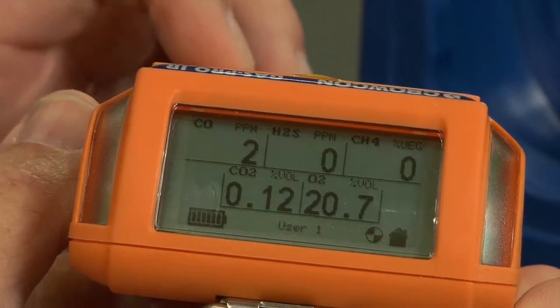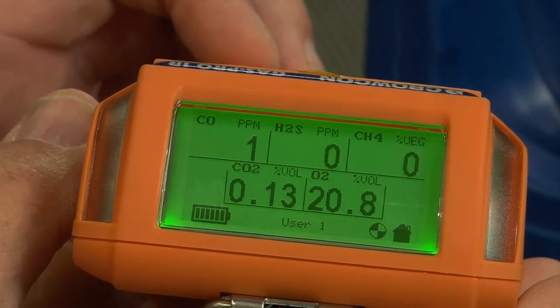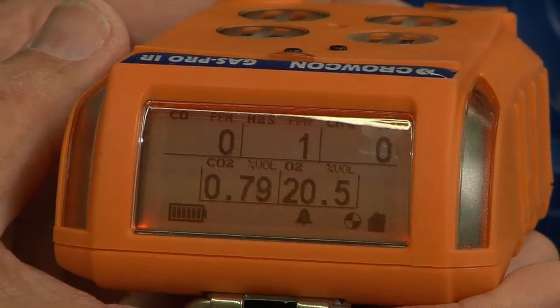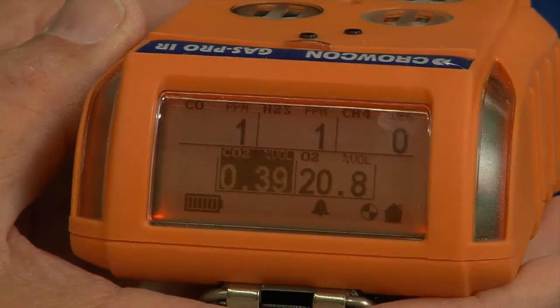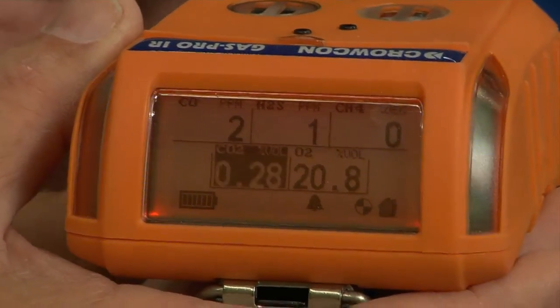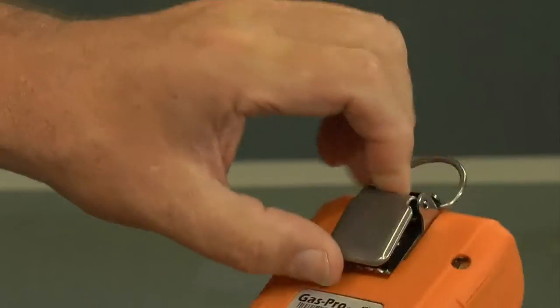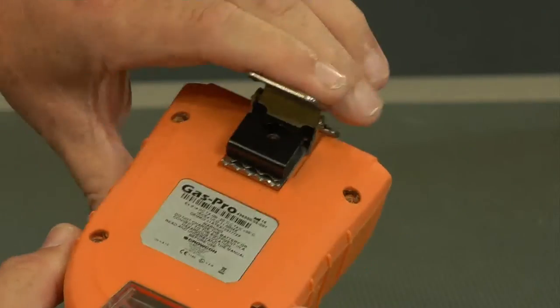Now I do my breath test — and now we are in the set alarm area. It alarms very strongly and is very loud, so that you can hear it in loud environments. I turn the sound off, but the optical alarm stays as long as the values are not back down to safe values. Now that is the case, and it shows normal. This device is pretty large, but it is a multi-function gas test device. I can also hang it around my neck or with the alligator clamp attach it to my belt or clothing. It saves the measured data, even after turning off — it is a very professional device.